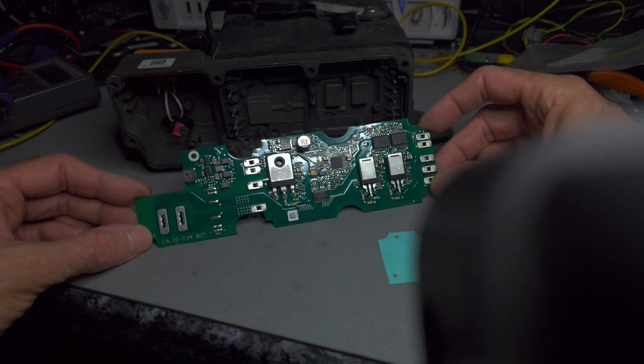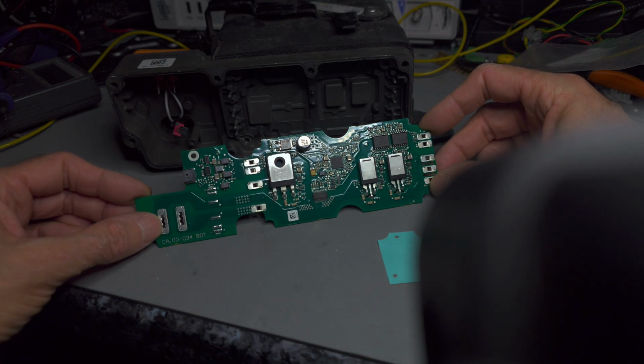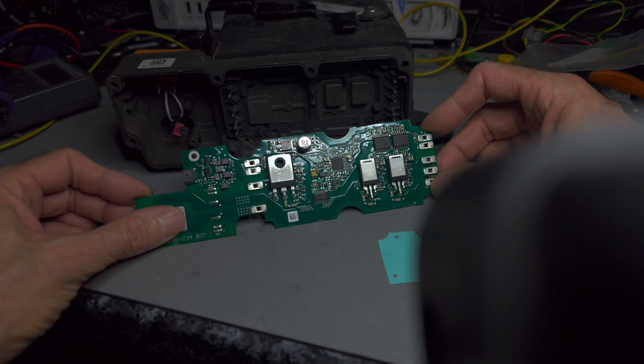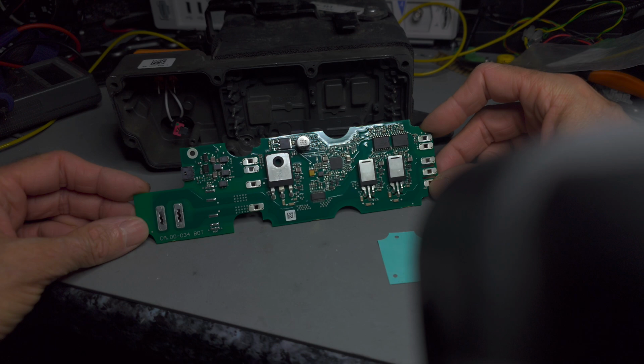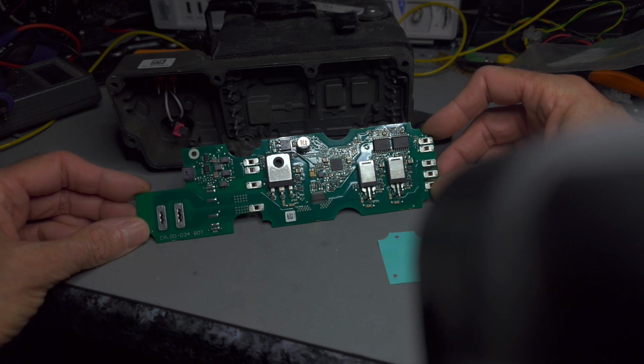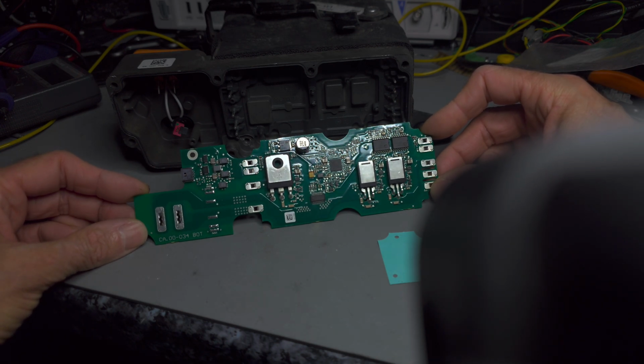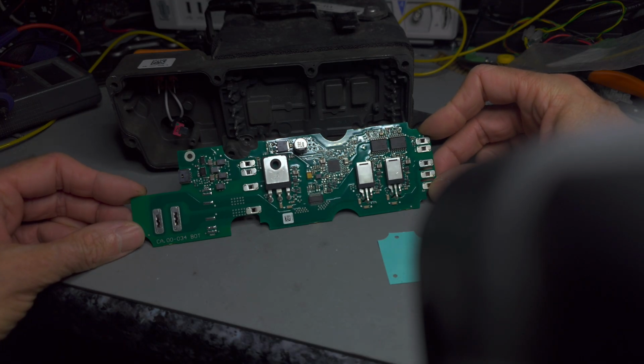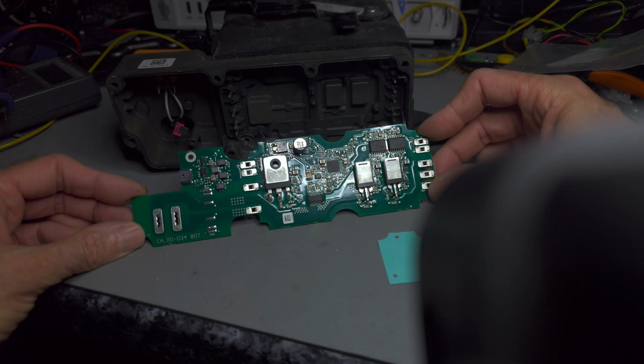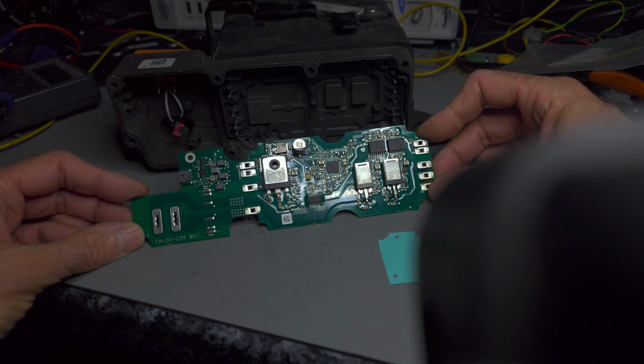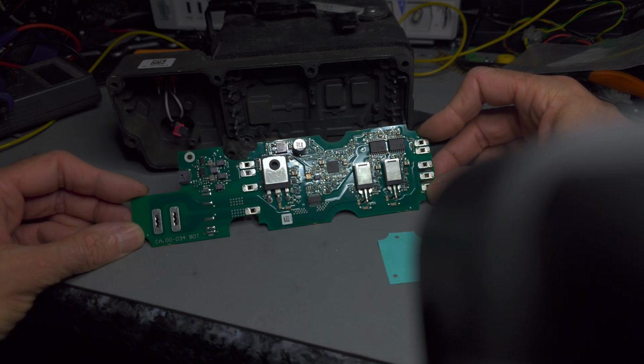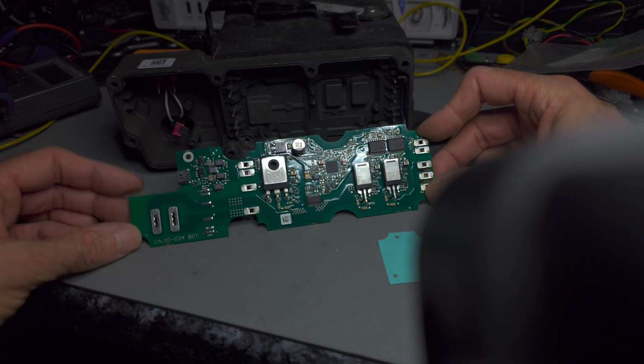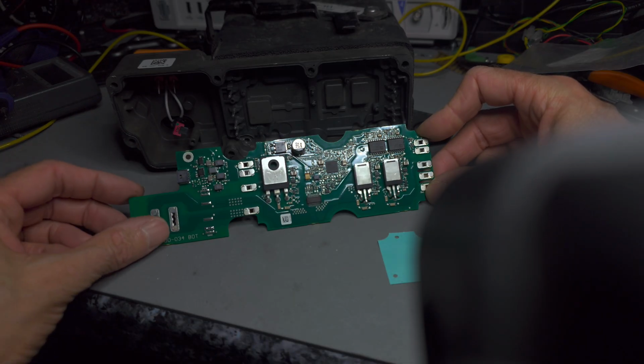Now, you can't just directly connect a 350 volt battery with hundreds or thousands of amps of current available to a set of empty capacitors, because you are effectively shorting the battery. At that instant, when you make that connection, the capacitors are at 0 volts, you've effectively made a short circuit and a fireworks display. So to allow the isolator contacts to be closed, you need to first reduce the voltage across the isolator contacts by relatively slowly charging those capacitors.